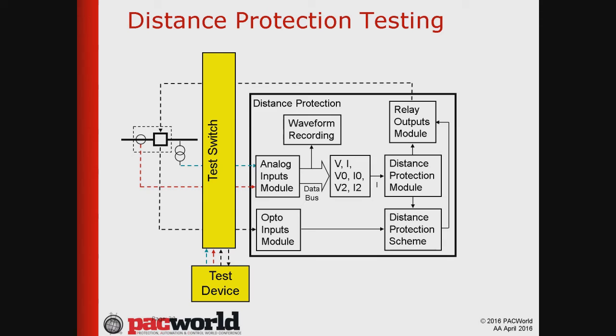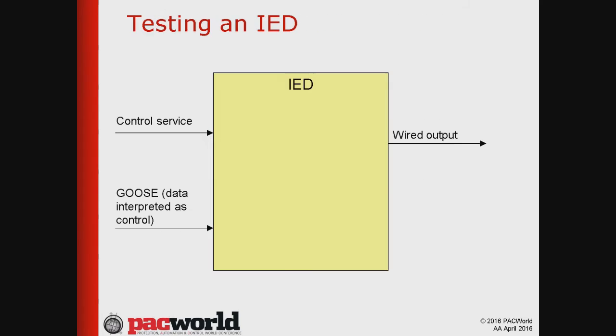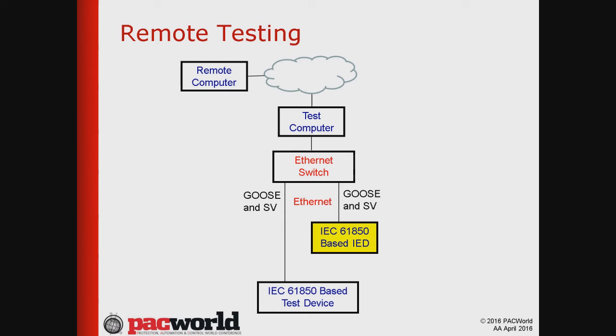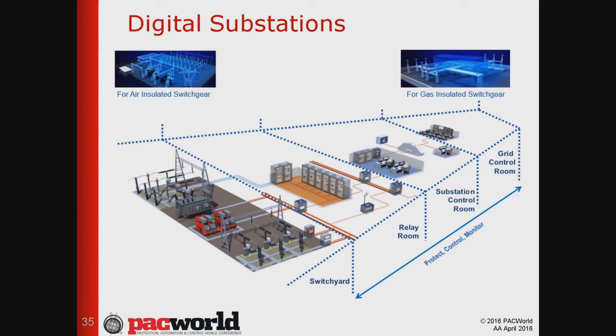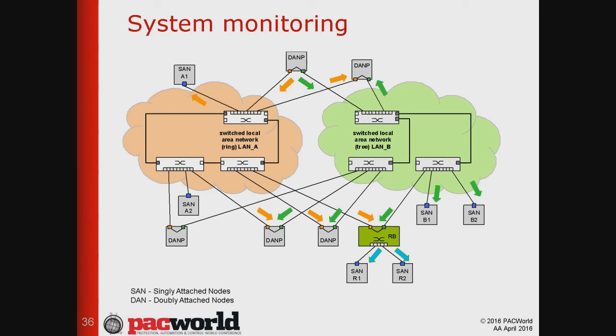Okay, this obviously cannot be done with conventional hardwired solutions because you have to have somebody physically switching the switches and connecting the test equipment. That is why we have different tools in IEC 61850 that allow us to implement this remote testing. So what do we do? We have a remote computer that connects through a secure connection over the cloud to a test computer and then runs the test plans in order to test the system. This is possible only within the IEC 61850 digital substation. And it is the digital substations that allow us to do that.